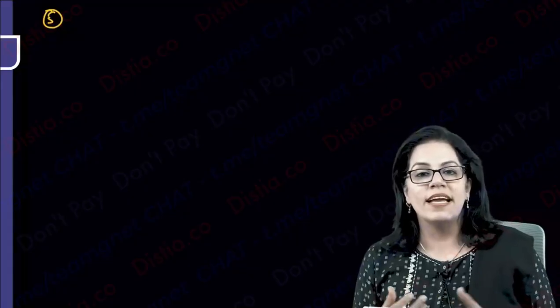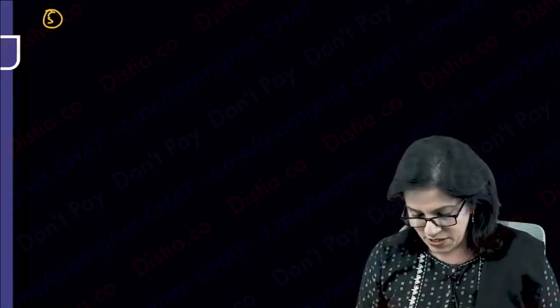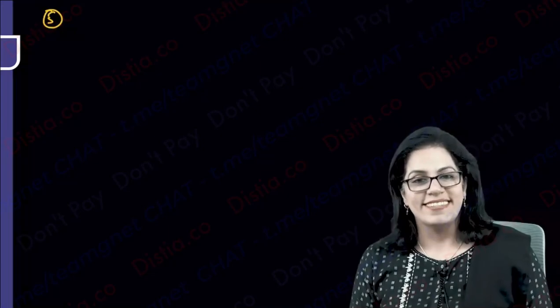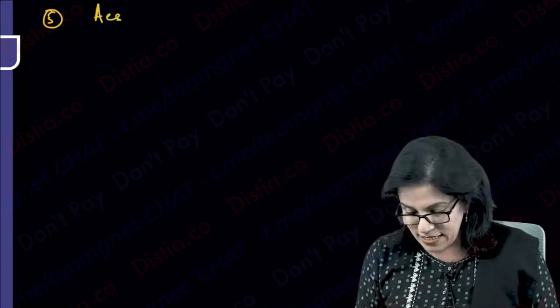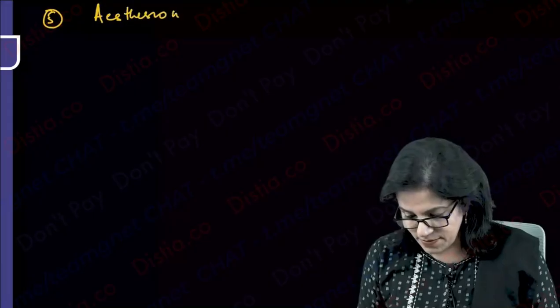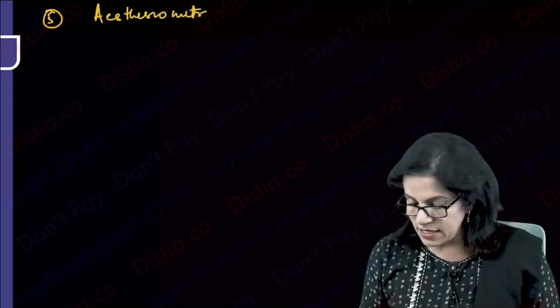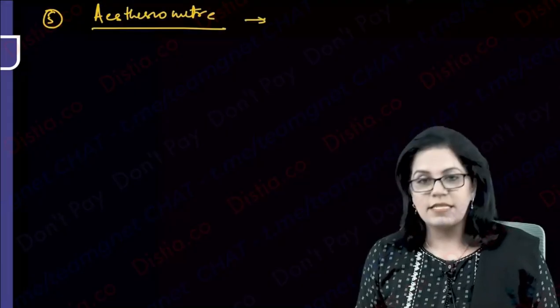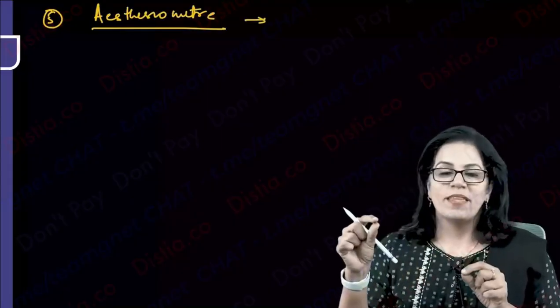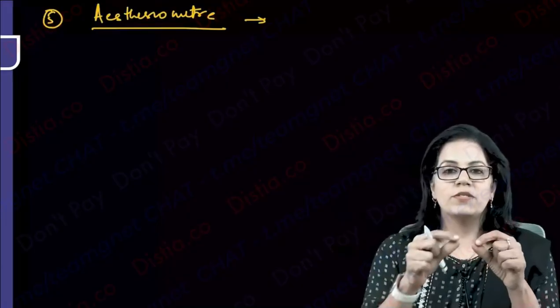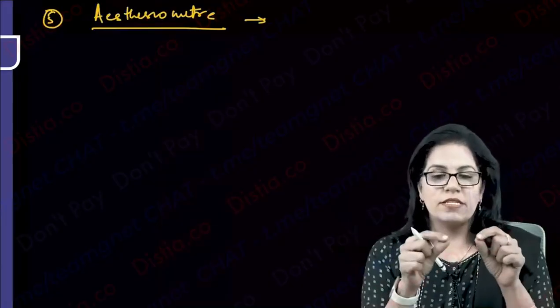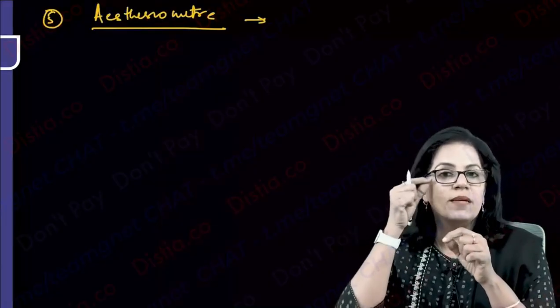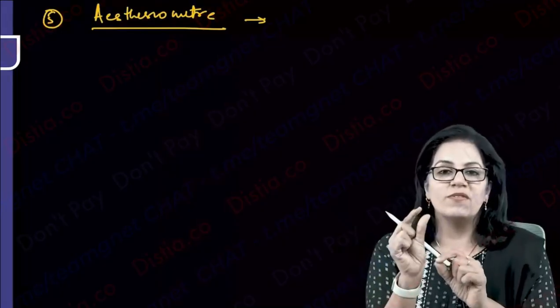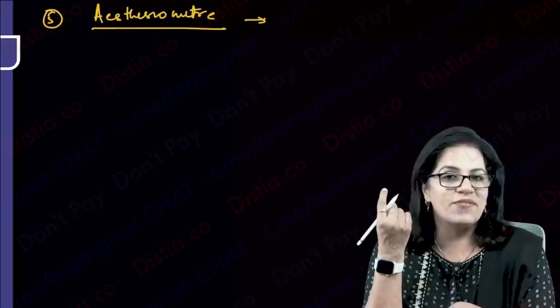This is going to give us the idea about the corneal sensation. But what is the instrument? That is called aesthesiometer. The aesthesiometer has a long filament, and you start at 60 mm, then decrease it by 0.5 centimeters and keep touching, seeing at what length of the filament the patient shows the blink reflex.